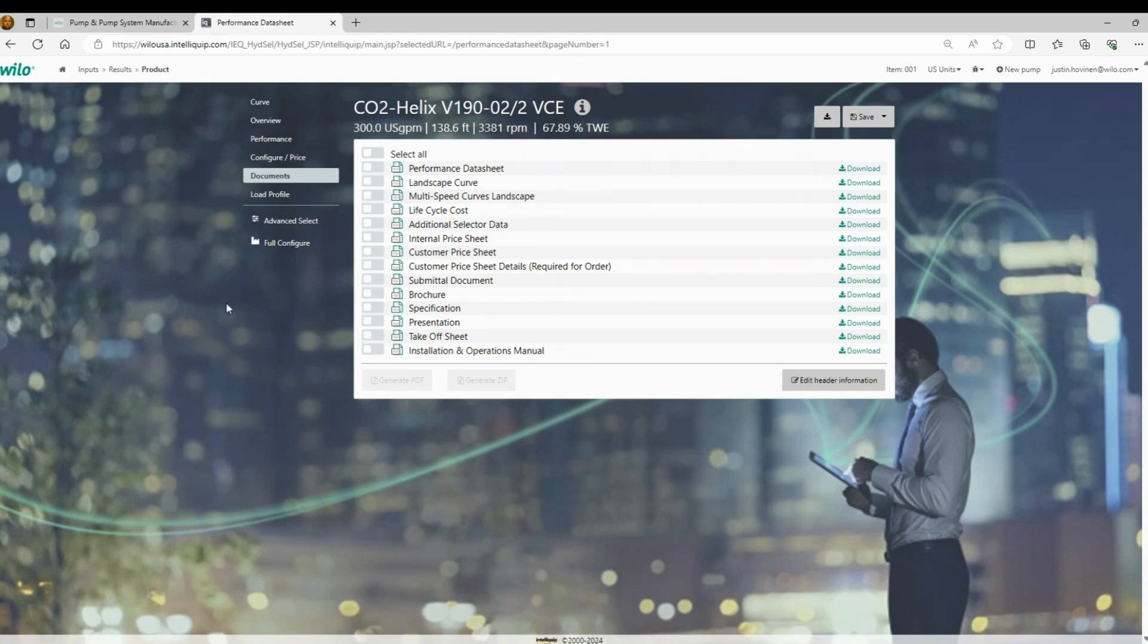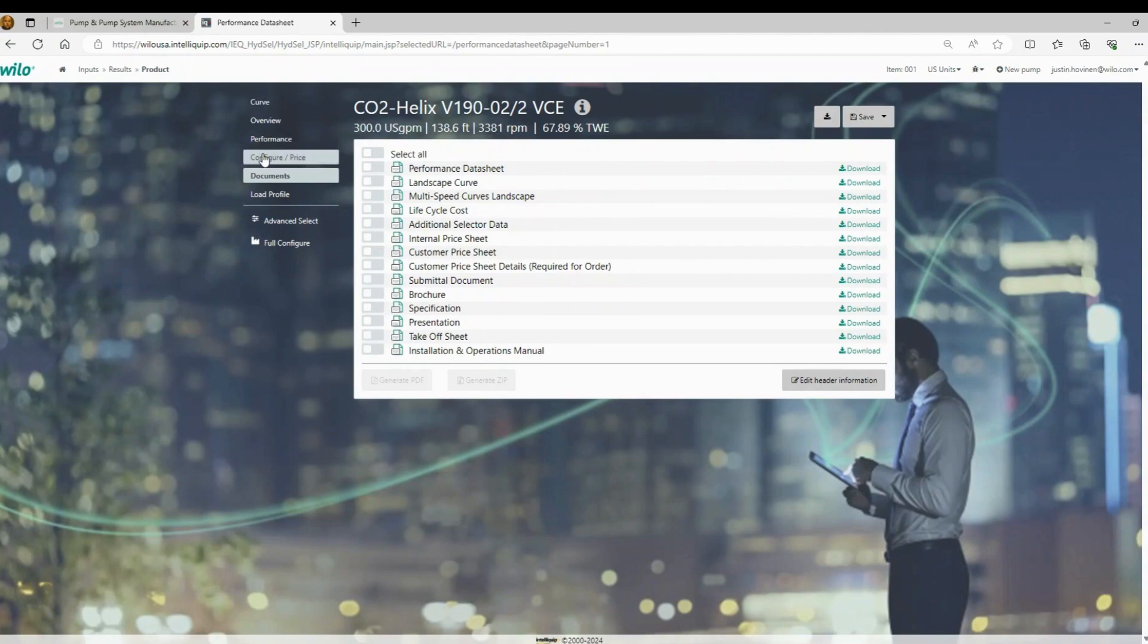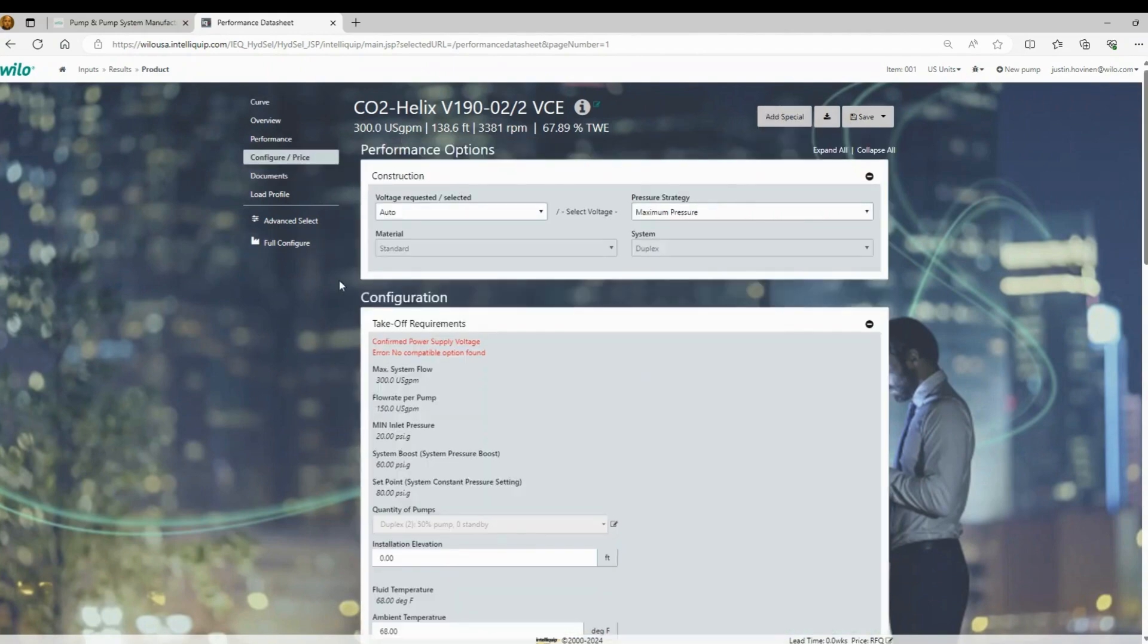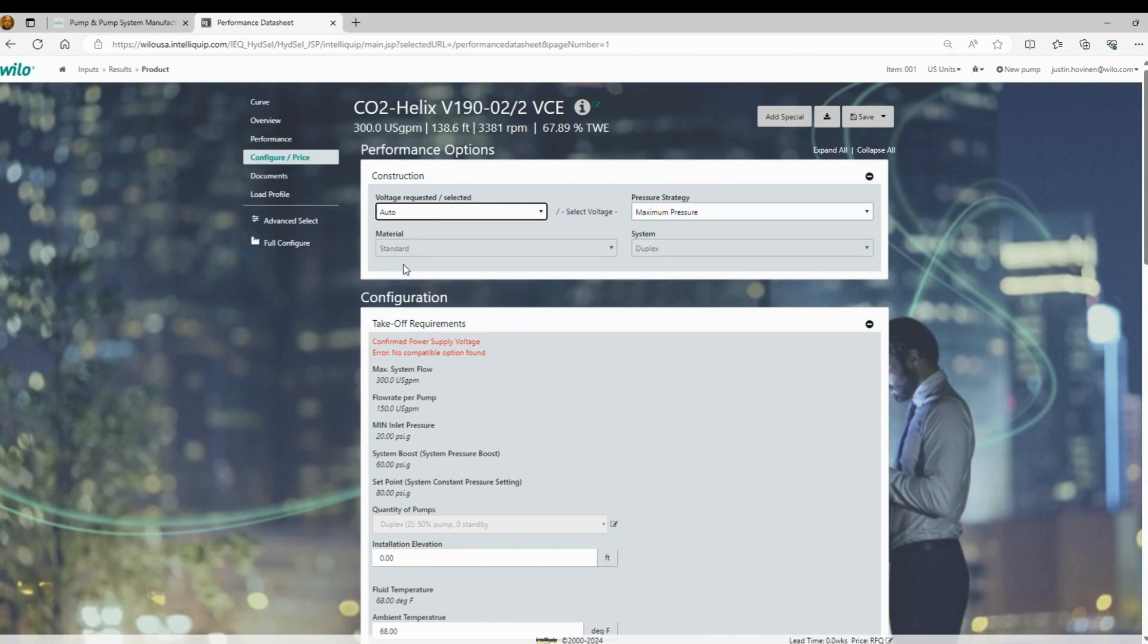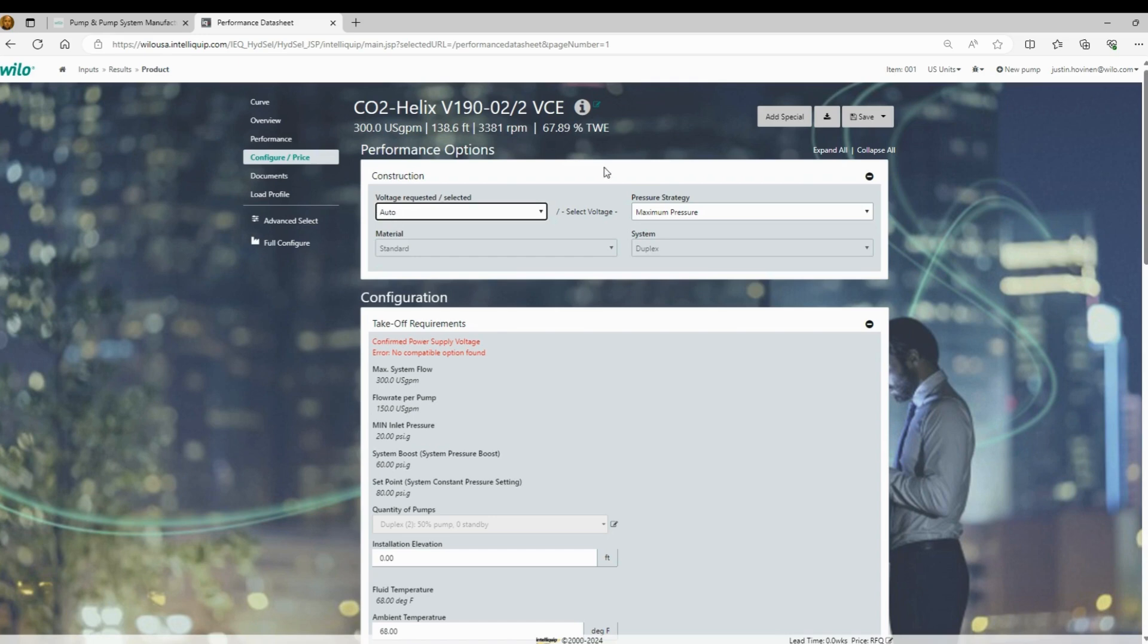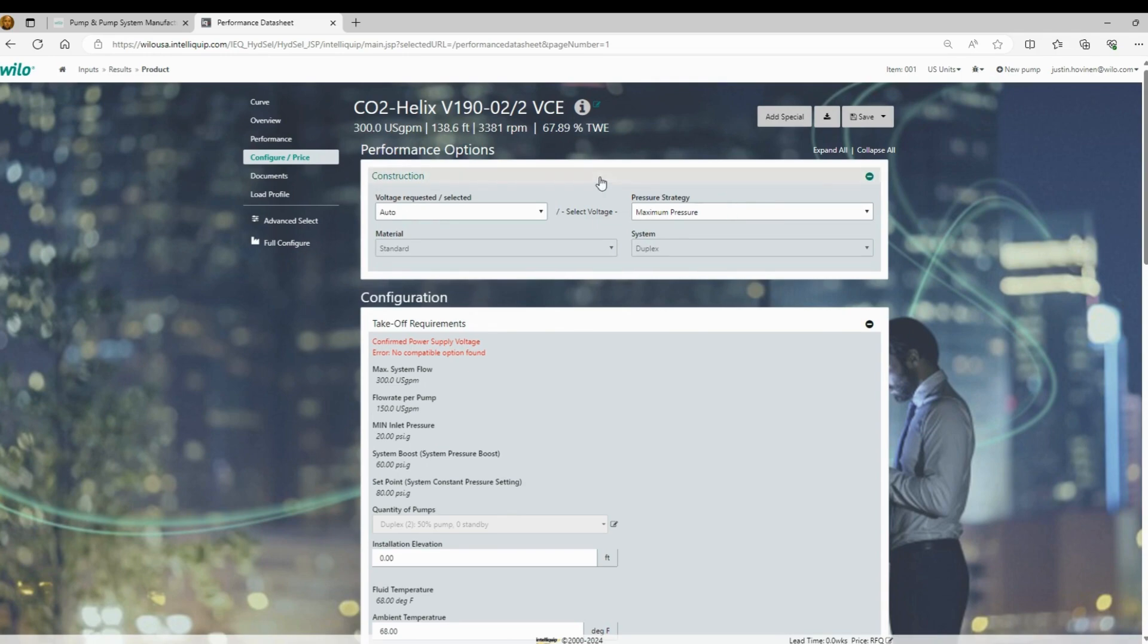So the next thing we're going to look at is the configuration tab. So you'll see here at the top, we have the first area is going to be the voltage. So you can choose your voltage. There's options here for three phase 208, three phase 460, and then three phase 575 volt. If the booster is smaller, you're going to also see single phase options available. There is an area over here to the right called the pressure strategy. Always leave that at maximum pressure, and that's just going to make sure that the system is designed for the pump running at shutoff.